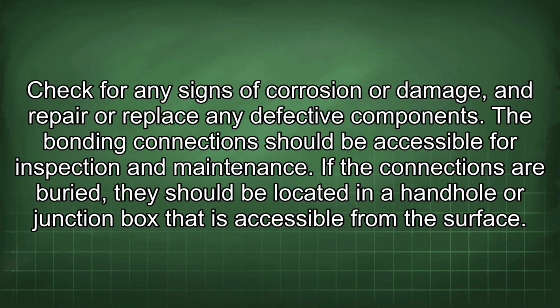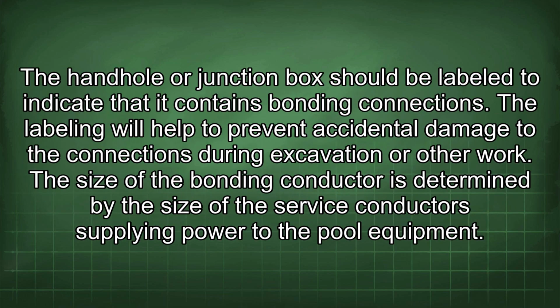If the connections are buried, they should be located in a handhole or junction box that is accessible from the surface. The handhole or junction box should be labeled to indicate that it contains bonding connections. The labeling will help to prevent accidental damage to the connections during excavation or other work.